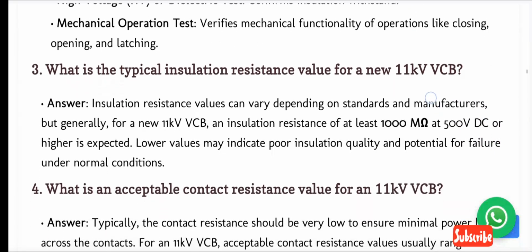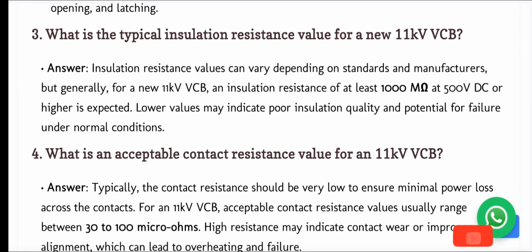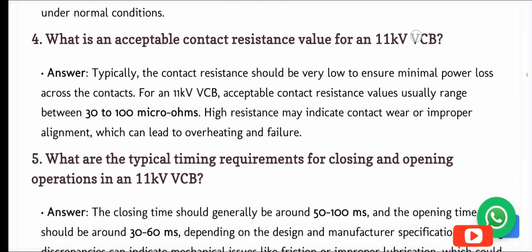3. What is the typical insulation resistance value for a new 11 kV VCB? Answer. Insulation resistance values can vary depending on standards and manufacturers, but generally, for a new 11 kV VCB, an insulation resistance of at least 1000 megaohms at 500 volts DC or higher is expected. Lower values may indicate poor insulation quality and potential for failure under normal conditions.